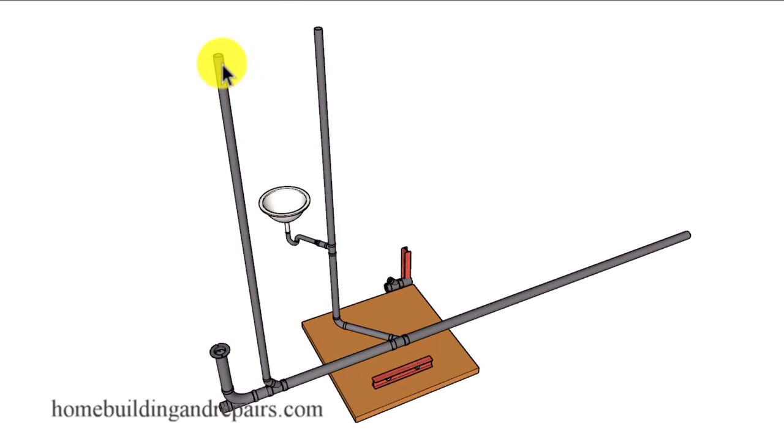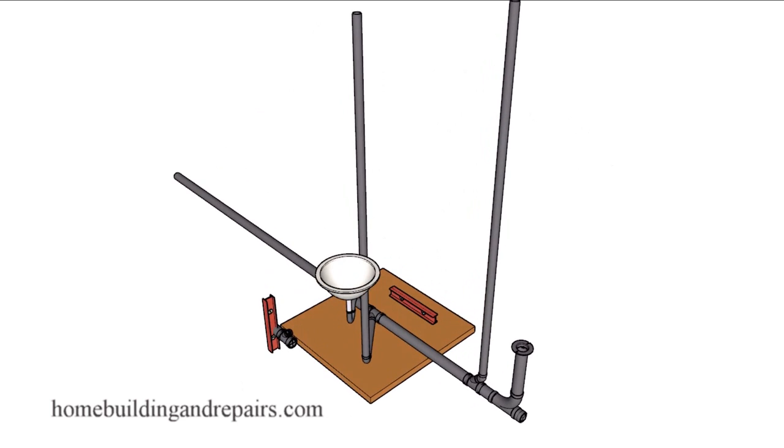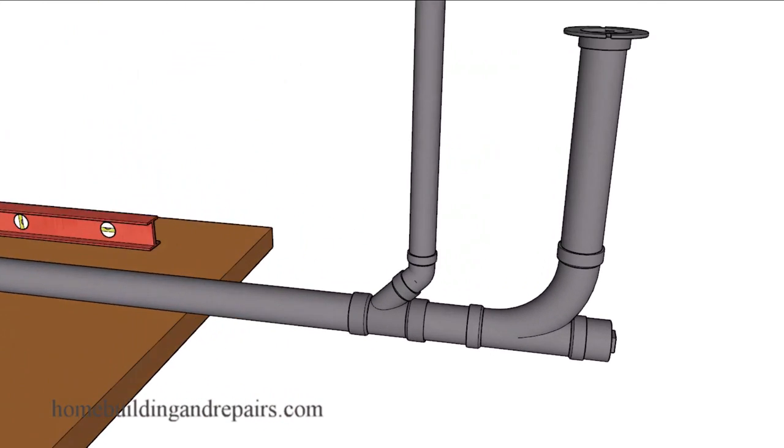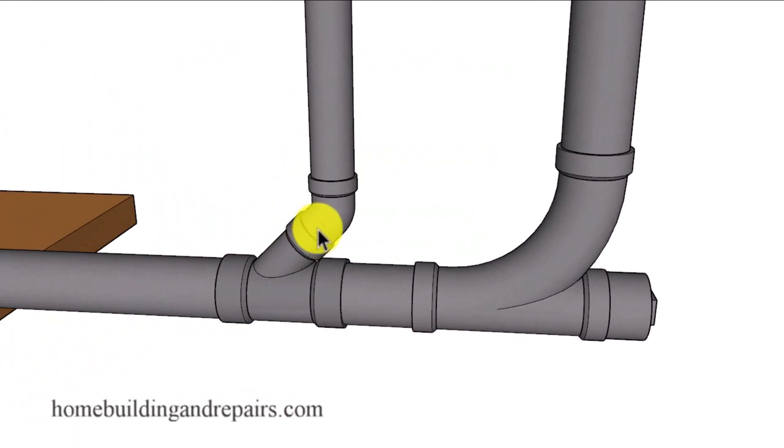Next up let's take a look at a vertical to a horizontal pipe connection. In this situation here, this is now the drain pipe. This is the vent for the toilet. And the building code requires it to be vertical or at the most, tilt it about 45 degrees. And I'm not talking about this tilt right here. This is just a way of connecting the vent to the drain pipe.